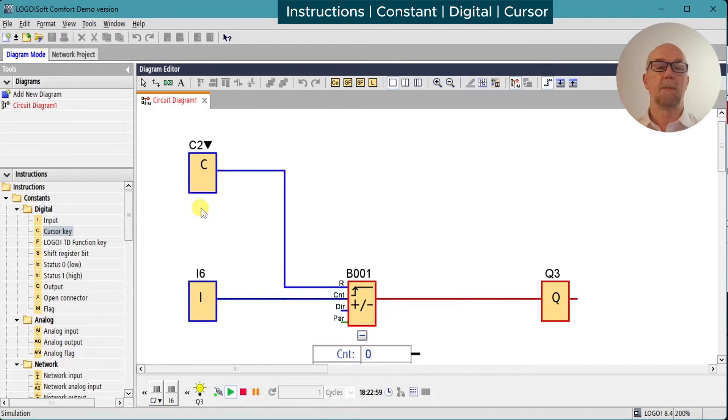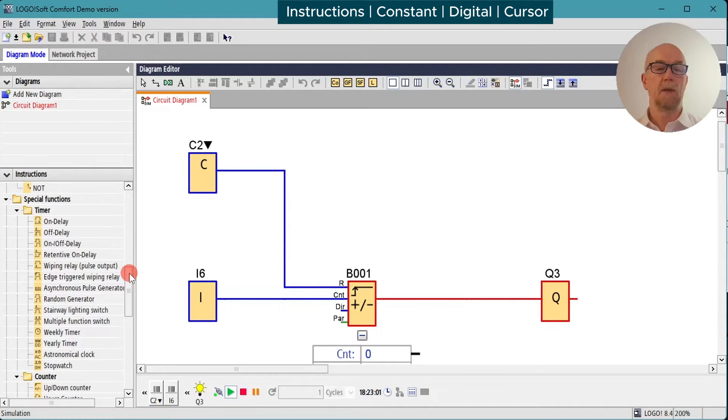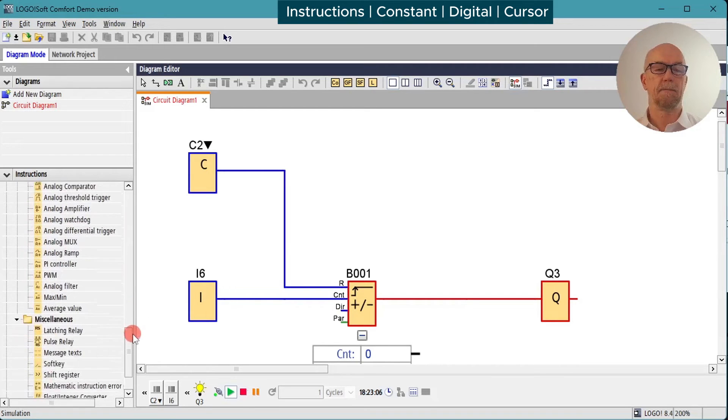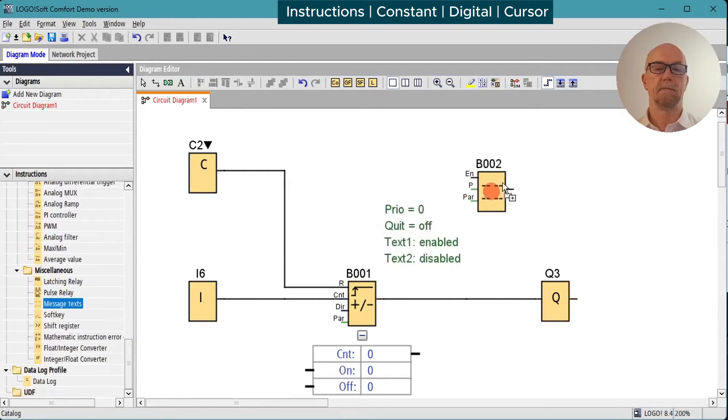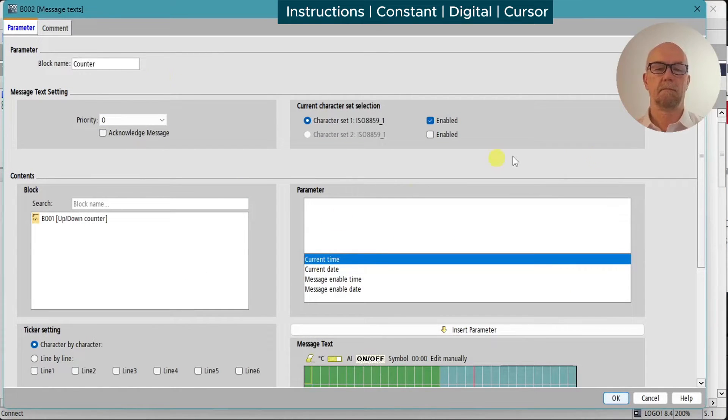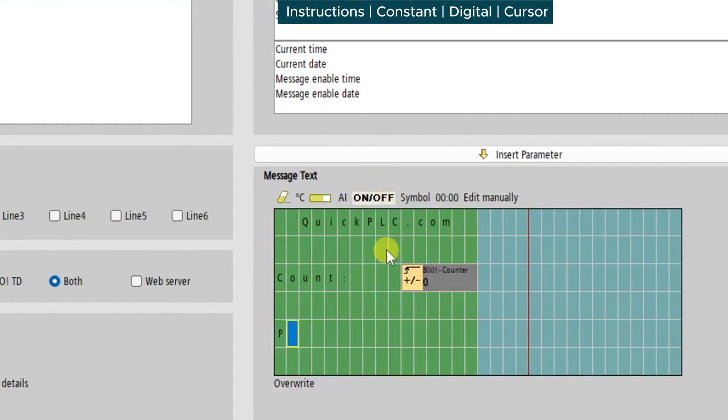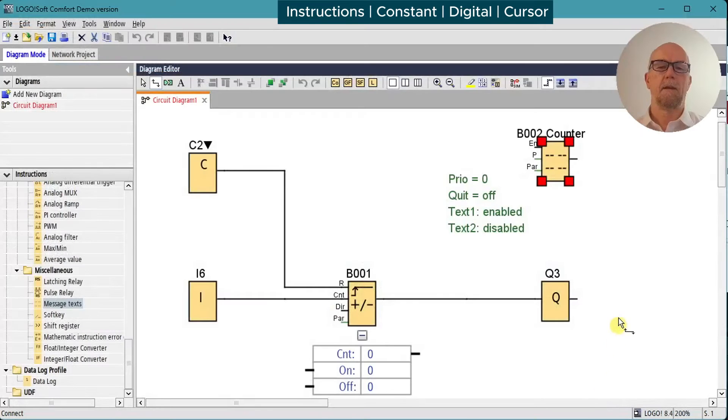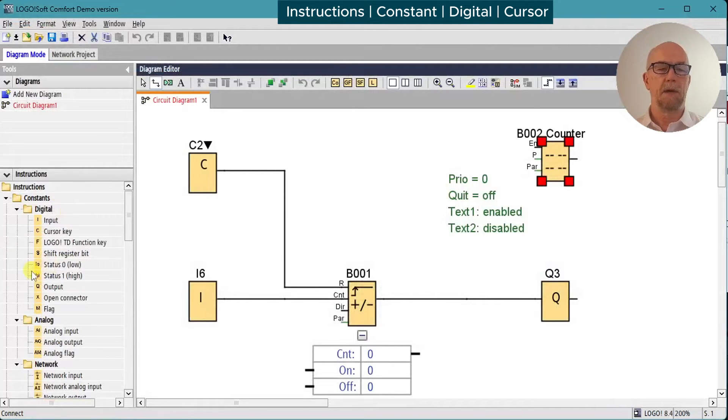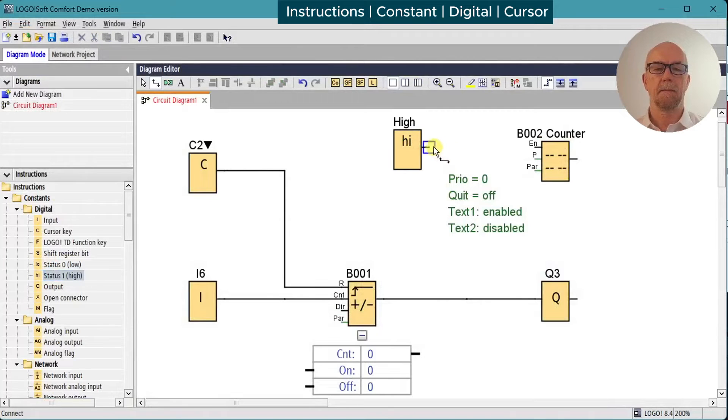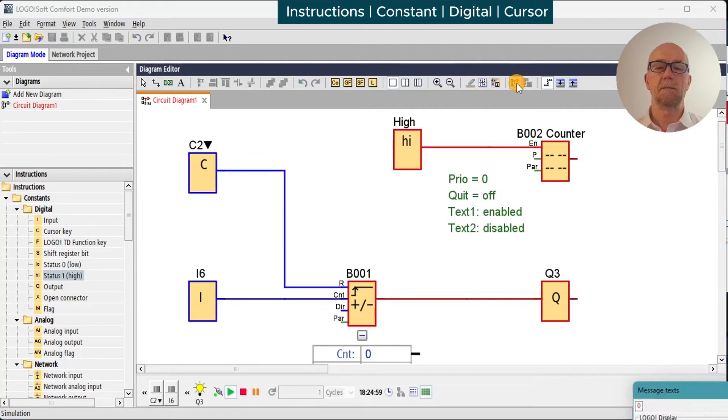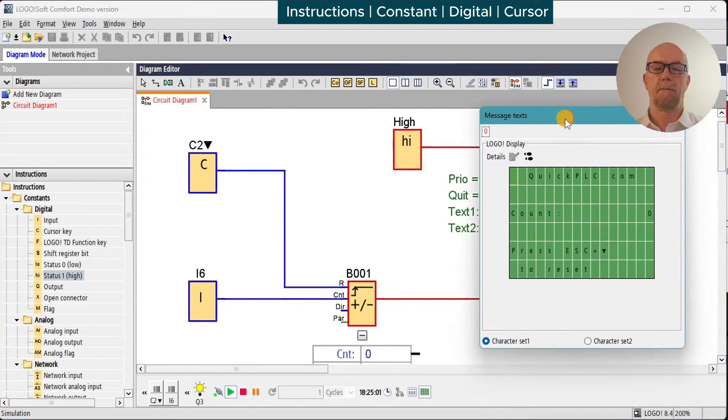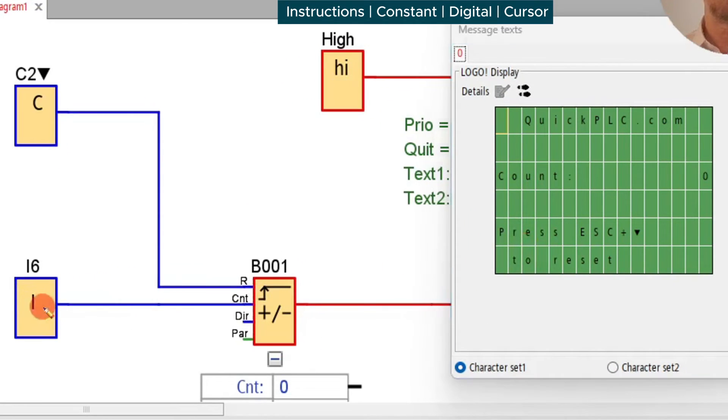We can set up an operator prompt for that so they know how to use the key. We'll add in a message text. The message text requires a logic one to keep it on, so we'll give that a status high. Run the simulation, and we can see the operator gets a nice little prompt here: one, two, three, four, press escape and down arrow, and reset.